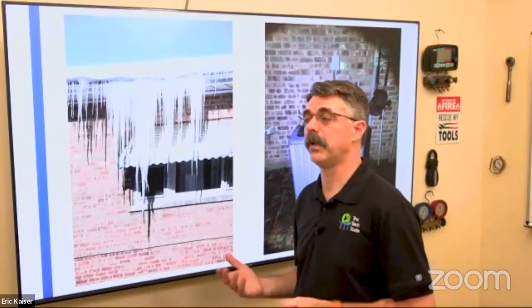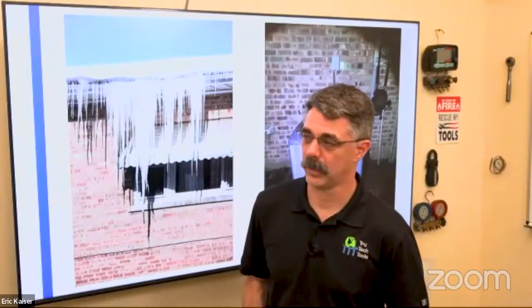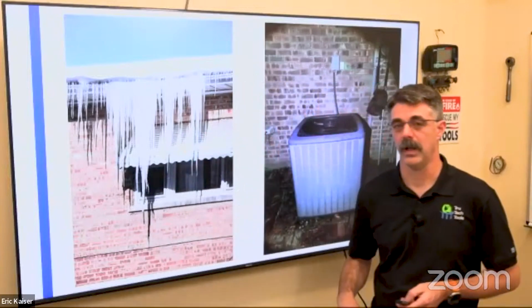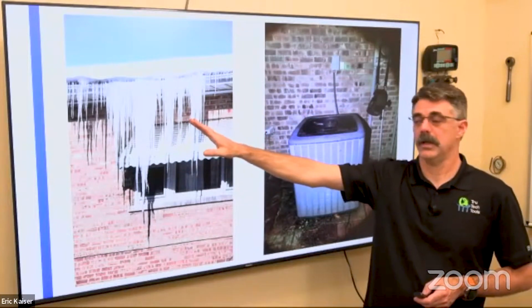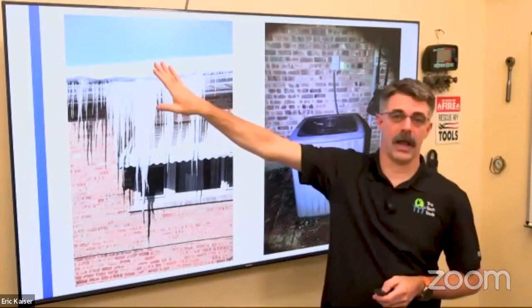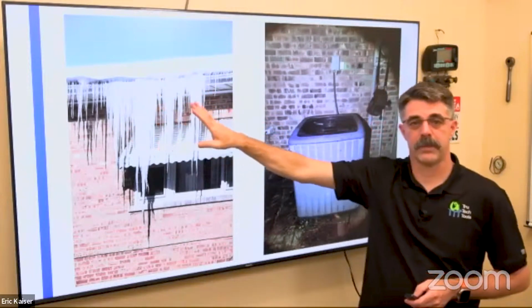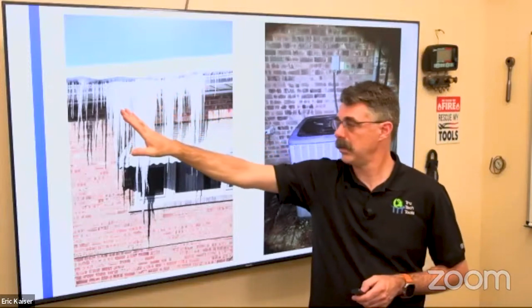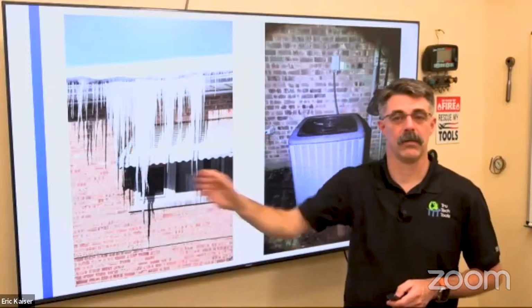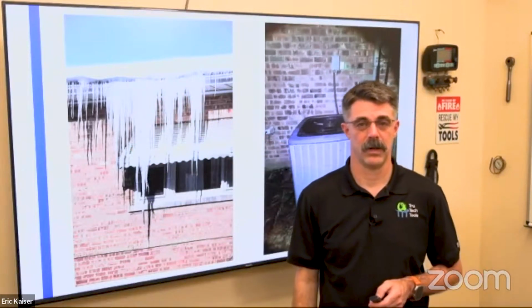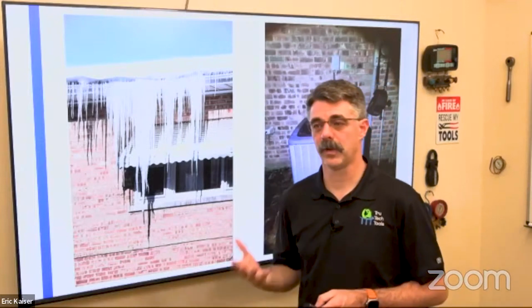Now, physical placement is a really, really big consideration with heat pumps. Couple things on placement. One, look up. If there's an eave or an overhang or anything else that can drop things on top of that heat pump, don't put it underneath that. Now, something else that occurs with a heat pump is that it does make a little bit of noise, especially at night, especially when it goes into defrost.